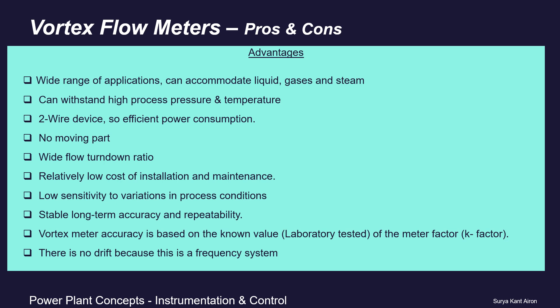Vortex meter accuracy is based on a known K-factor, where F = K × V — the frequency of vortex generation equals the K-factor constant multiplied by fluid velocity. This K-factor for each instrument is calculated and tested in the laboratory and is marked on the instrument nameplate. There is no drift because this is a frequency-based system.